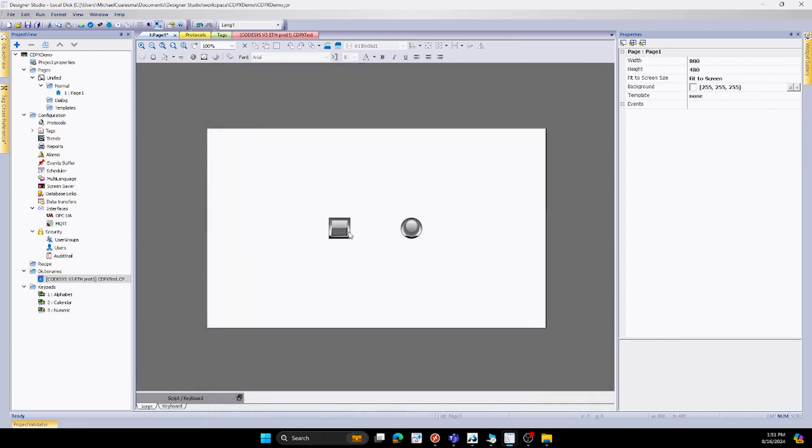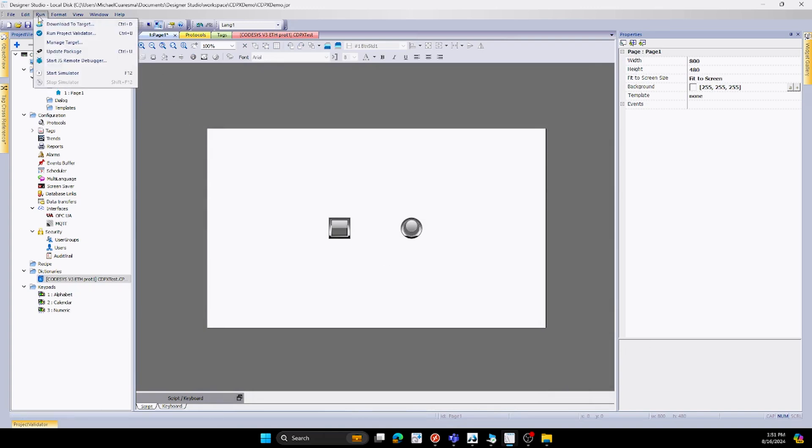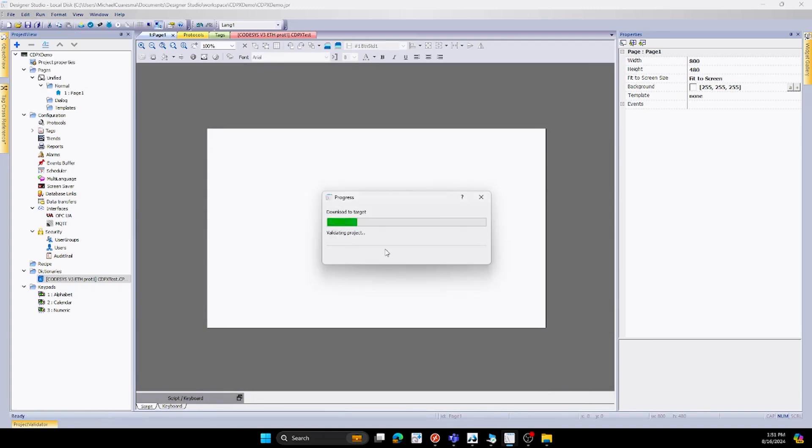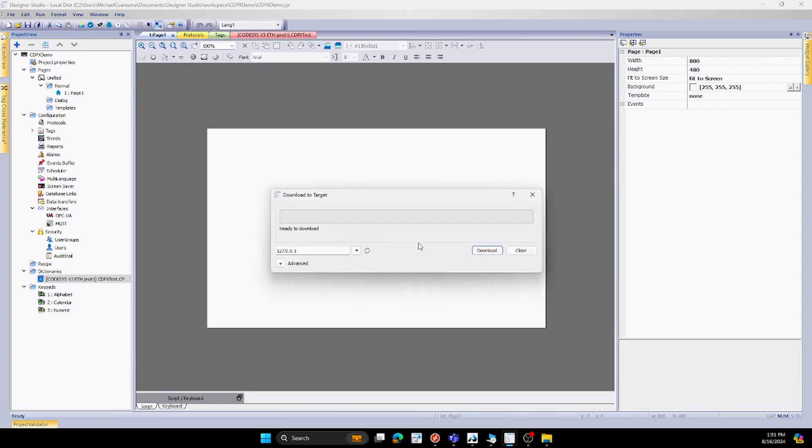For my LED, I'll do the same thing. Go to value, hit my plus button, and hit light. Now my project is completely set up with my buttons being linked to my tags. Next, what I'll do is hit my run button and download to target. I'll select the HMI that I have, 192.168.4.20, and hit download.